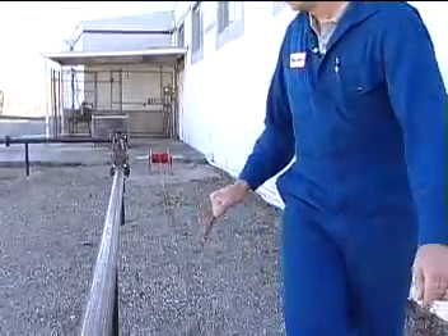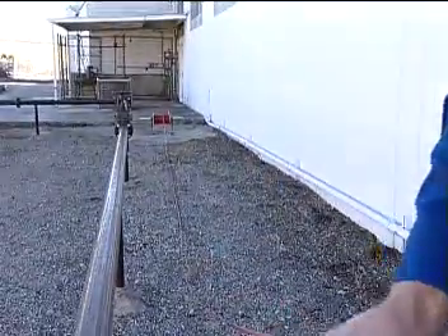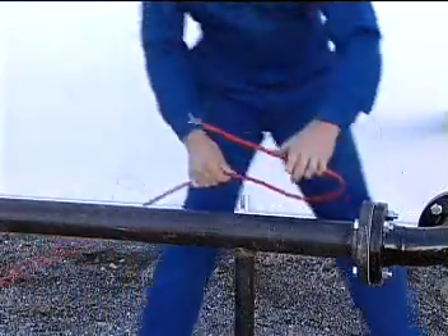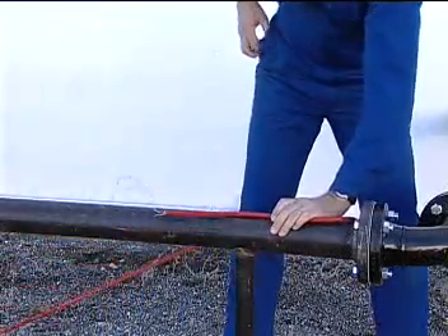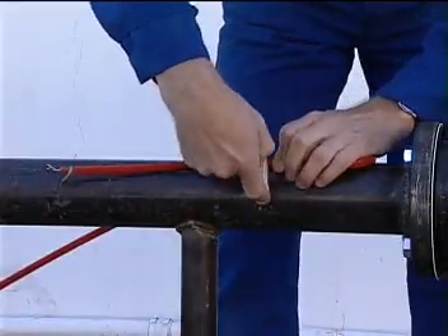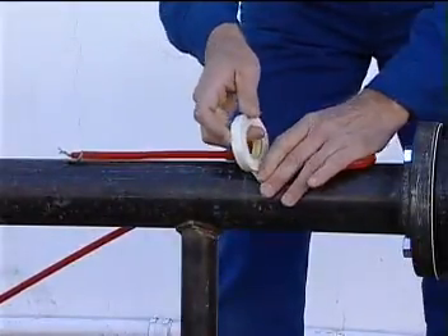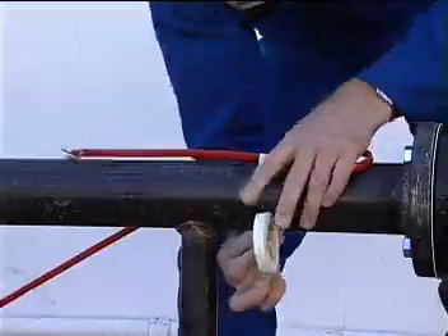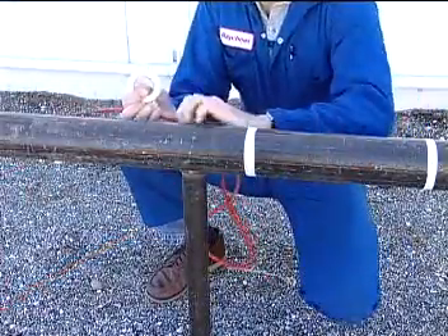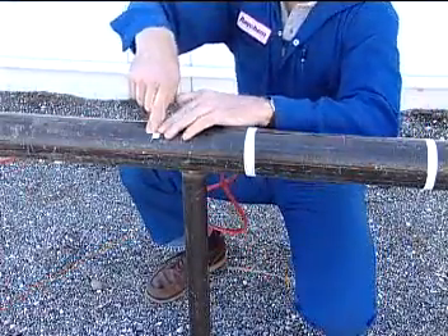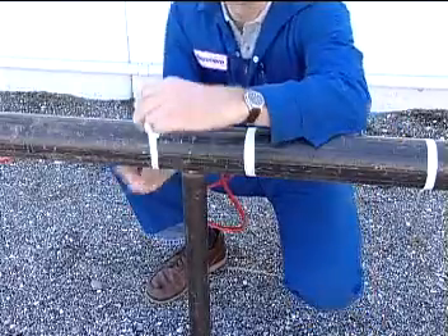As you pull the cable out, loosely string it over any supports. If the cable has to be temporarily placed on the ground during this process, make sure that it doesn't get walked on or run over, which could cause mechanical damage. When you reach the end of the circuit, leave about 1.5 feet of extra cable on the end as a service loop for the end seal. Then, secure the cable to the pipe with tape. The extra cable of the service loop ensures that you'll have enough new cable available if a connector needs to be replaced.